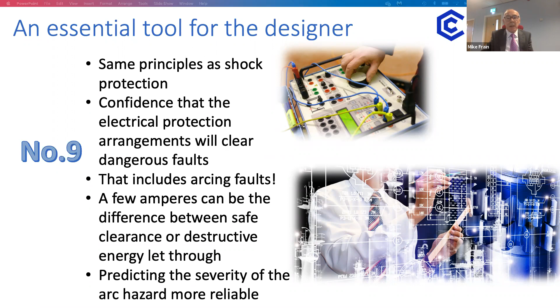Predicting the severity of arc flash hazards has become more reliable, largely because of empirical evidence gathered in laboratory situations where it's applied. IEEE 1584 was conducted on 2,000 high power laboratory experiments between 208 volts and up to 15,000 volts, so these predictions are a bit more reliable and less theoretical than they may have been at one time.